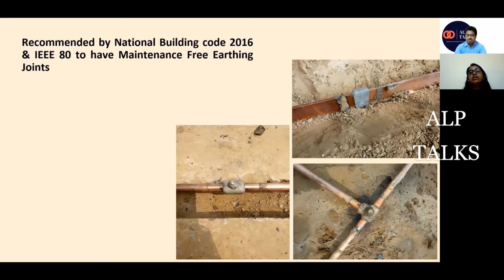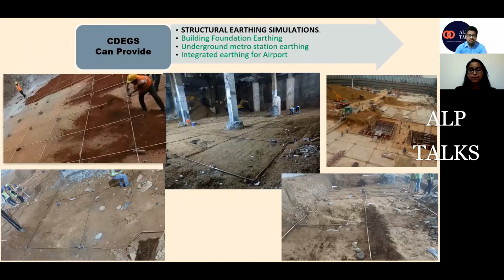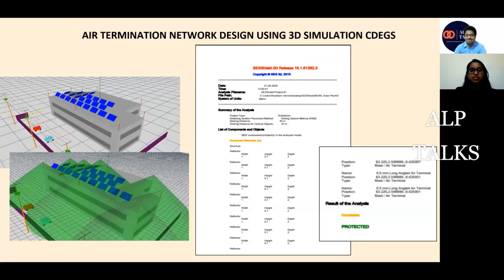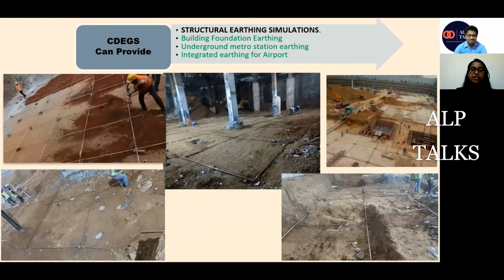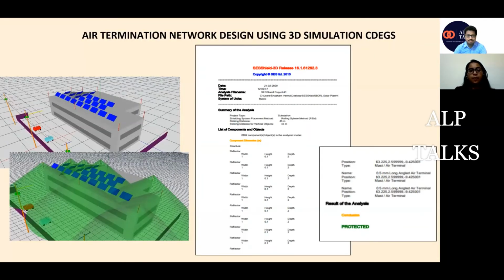Any type of joint, whether it is pipe to rod, strip to rod, strip to strip, or strip to stranded conductor, any kind of joint can be made by exothermic welding. So this was all about the earthing system. These are some of the pictures of earthing grids which we installed for metros or for underground structural high-rise buildings. In this way, we lay the earthing grid and we do the exothermic welding at every corner and every joint.